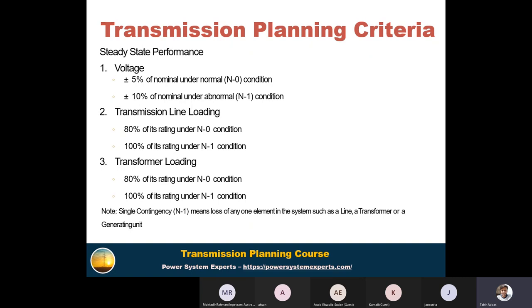Under N minus one condition, the voltage range is higher, that is 10% in per unit, from 0.9 to 1.1 per unit. So these are the criteria for voltage. The next criteria is related to transmission line loading. Under N minus zero condition, the limit is 80% of its rating, so the line is loaded only 80%. When the line is loaded more than 80%, we need to augment that conductor, string that conductor, change that conductor, or propose another solution. Next, under N minus one condition, we can accept the thermal limit, that is 100% of its rating.